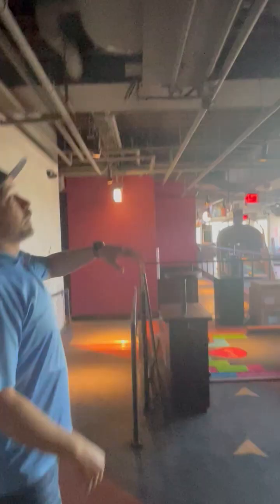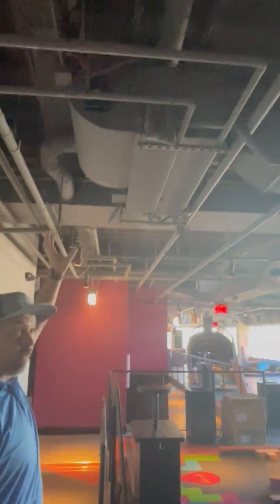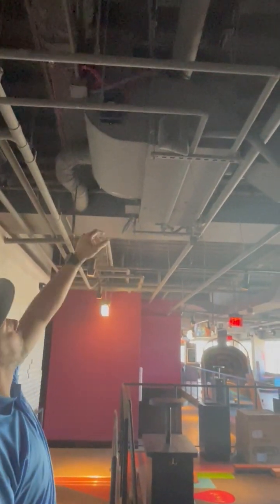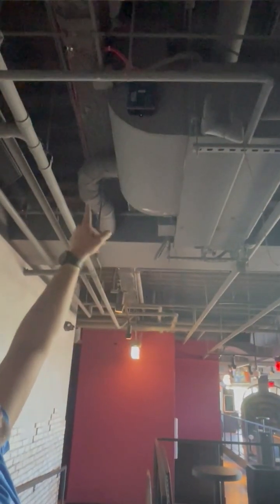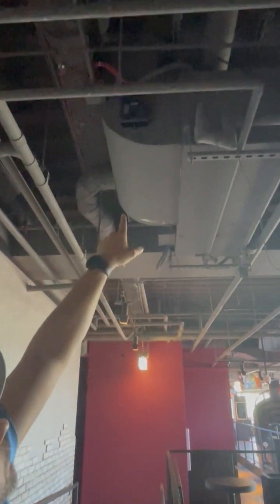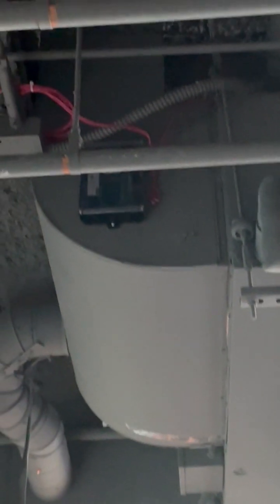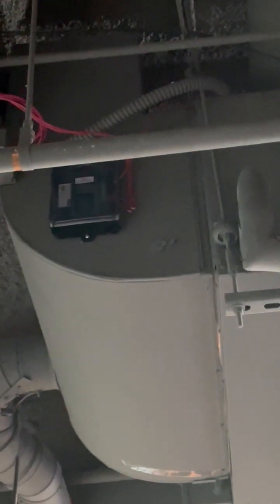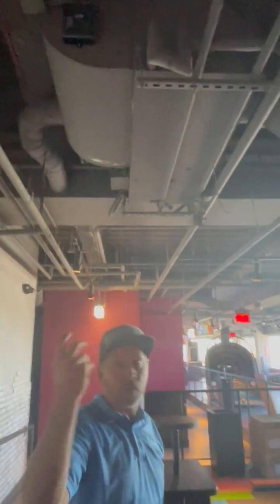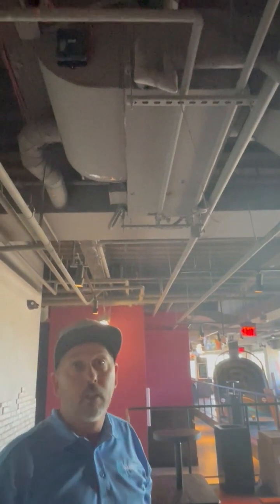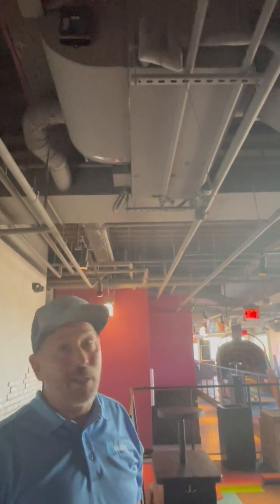Here we have the chilled water fan coil. The only true maintenance you'll have on these is the filter section. It's right here next to the smoke detector - you can see a little access point on the side of the return elbow. You're going to check those at least once a month. The elbow is the part pointing up - right above my finger is where the filter access is. You'll unclip the little levers, open up the panel, and slide your filter out. I'd recommend checking them once a month and maintaining them as needed.